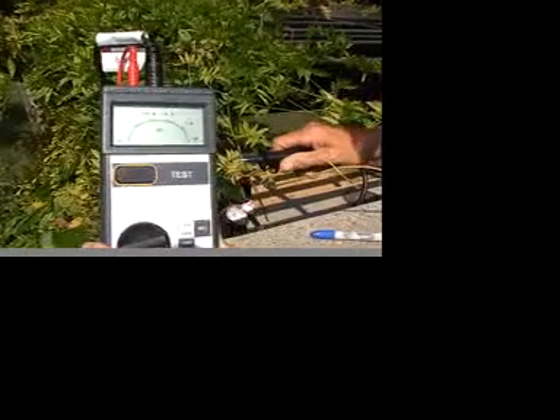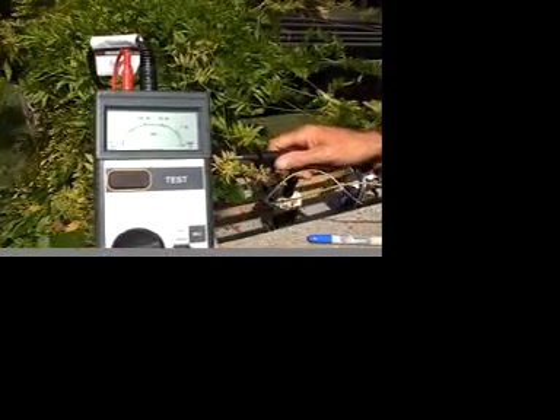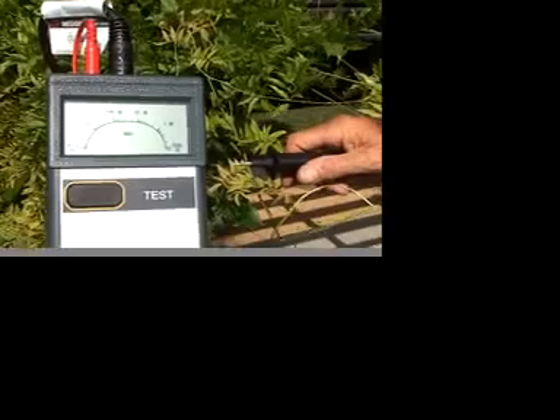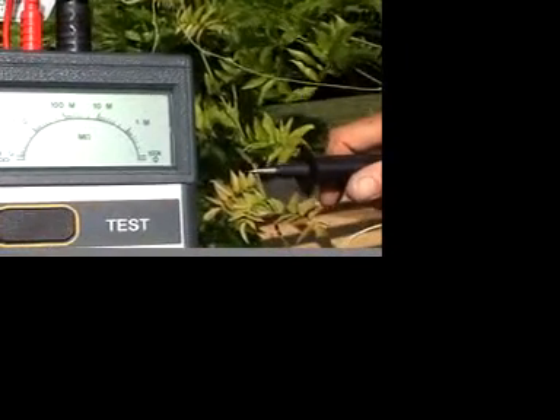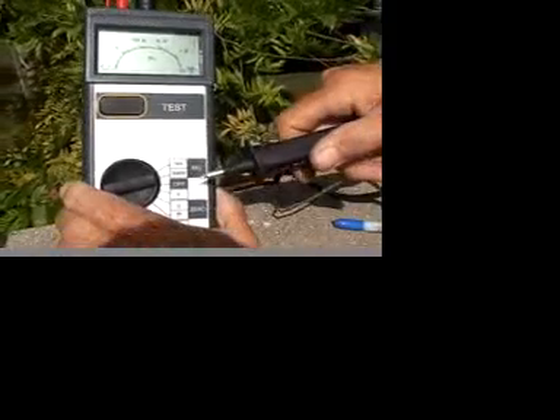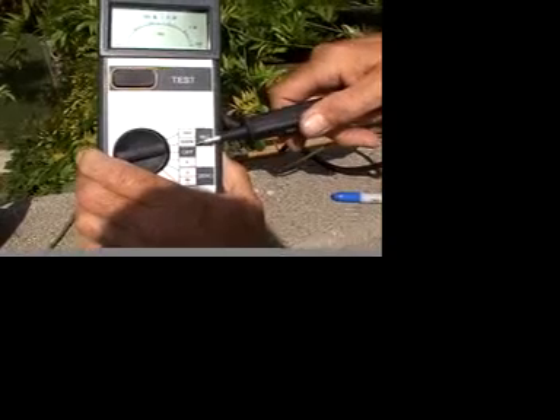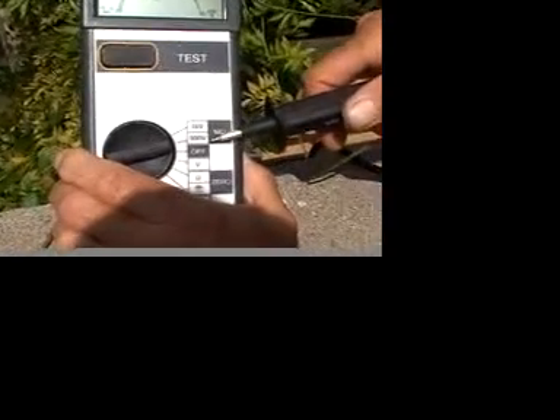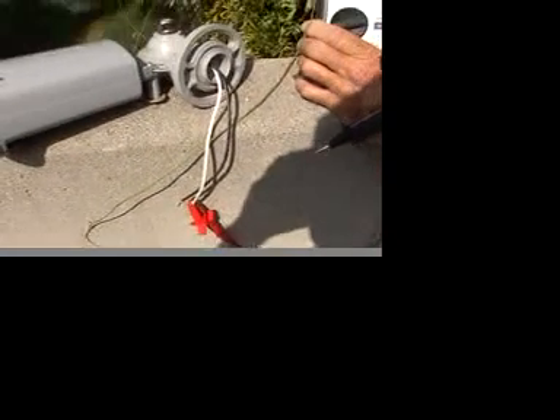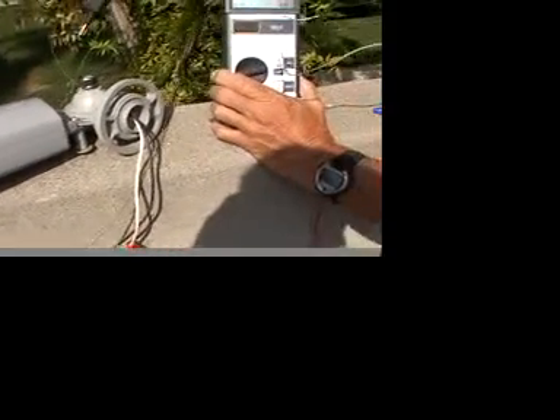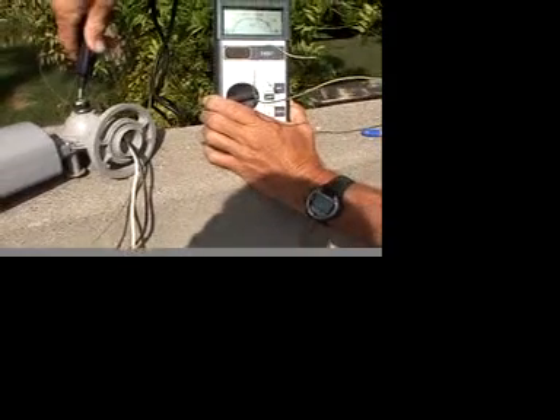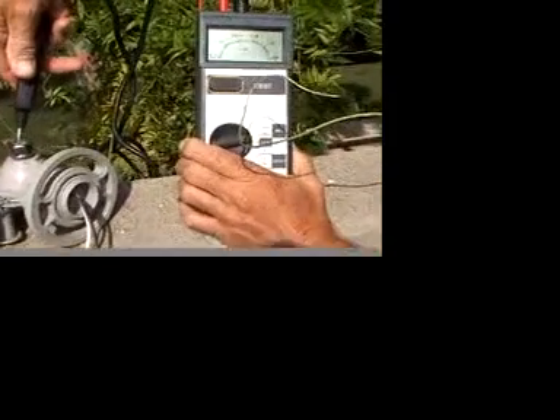This is a megger, also called a megohmmeter. It applies 500 volts or 1000 volts to test the insulation. Right now I have it on the 500 volt range, and I have the clip attached to one wire that goes to the socket. And if I check the insulation to ground, I merely connect the probe to ground and push the button.